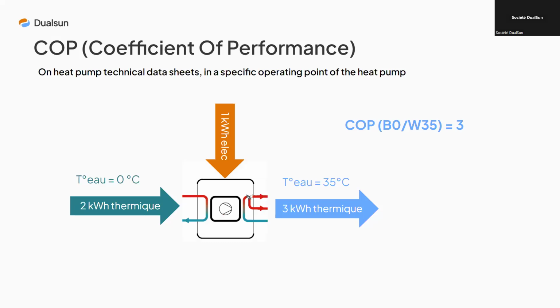Then there are the various terms used in the heat pump world. So we're going to see them. First, we have COP, coefficient of performance. The COP is defined as the number of kilowatts of heat I obtain from my production circuits divided by the number of kilowatts of electricity required for the thermodynamic cycle, compression, consumption, circulator, etc. This COP is shown on the data sheets for the heat pumps at a specific operating point, and very often B0W35, which means that the water temperature at the collector inlet is 0 degrees and the heating water production temperature is 35 degrees.